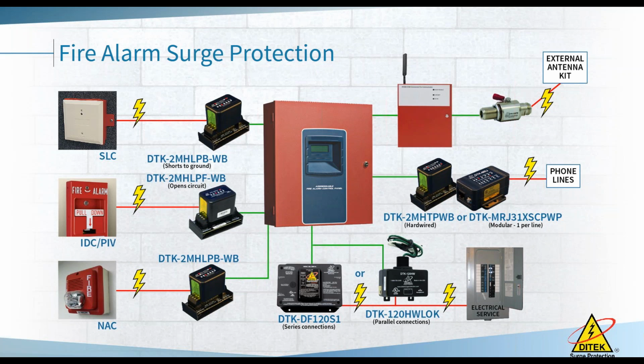I would say 50-50 when I'm in the field. When I ask service techs and I ask inspection crews, hey, is it part of your punch list to make sure the HW light's still on? And they all just kind of look around and look at each other. So I think it's left off quite a bit. So if you're using those, I would just say, for your own sake, make sure the light's still on, because if it's not, the next surge that comes through cooks your panel, and then the customer is looking at you going, okay, why did I pay for this surge protection? And then I get the phone call.